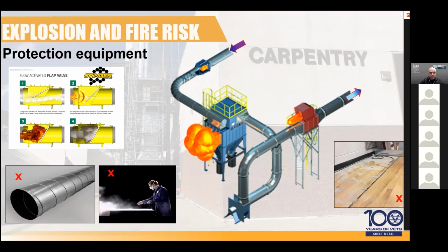So you want to make sure that when you look at the place, they are doing their proper maintenance and essentially cleaning the floors, cleaning the cable trays. 5%, 1/8 of an inch is not a lot. So if you have cable trays that have a little bit of dust, or any of that, this could be sufficient to create a hazard in a shop where the explosion would actually cause severe damage.